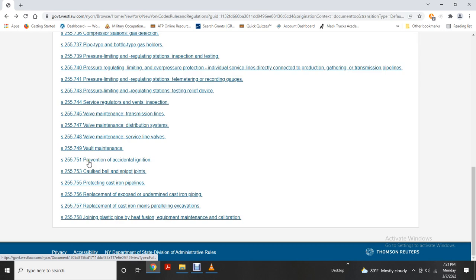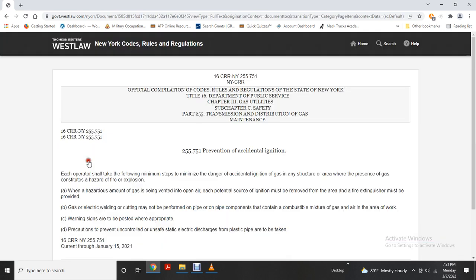Alright, preventing accidental ignition. Each operator shall take the following minimum steps to minimize danger and accidental ignition of the gas in any structure or area where the presence of the gas constitutes a hazard of fire or explosion. Where a hazardous amount of gas is being vented into the open air, each potential source of ignition must be removed from the area, and a fire extinguisher must be provided.